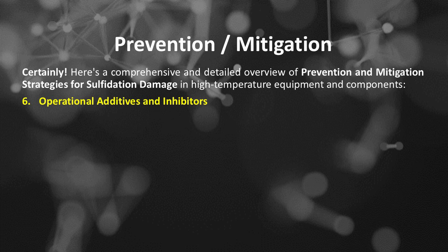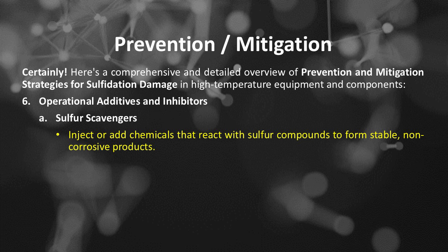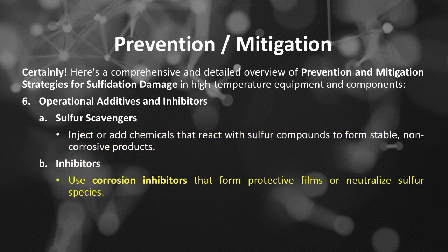Number 6 of prevention and mitigation strategies for sulfidation damage in high-temperature equipment and components is operational additives and inhibitors. Number A, sulfur scavengers. Inject or add chemicals that react with sulfur compounds to form stable, non-corrosive products. Number B, inhibitors. Use corrosion inhibitors that form protective films or neutralize sulfur species.